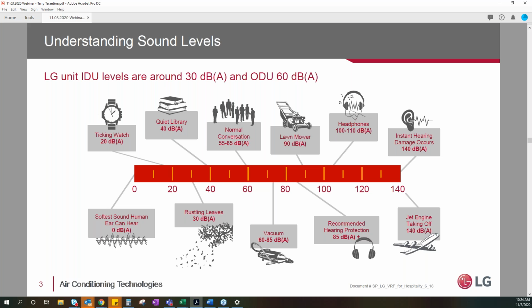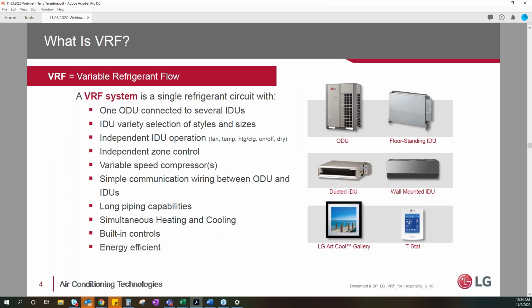And here's a chart kind of showing the decibel levels. We said that that 10-ton unit was 59 dBA. So if you look towards the middle there, that's about normal conversation level. And again, that's a 10-ton outdoor unit running locked in at 60 hertz. So typically they're running less than 60 hertz. They're even quieter than that. And they show some different options there.